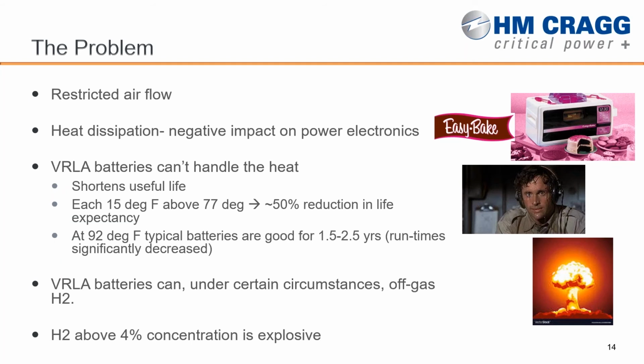VRLA batteries, for example, all of the ratings for life expectancy and what the end of life runtime would be is all calculated based on maintaining a perfect 77 degrees for the entire lifespan of the battery. But for every 15 degrees above 77 degrees you go, you can see about a 50% reduction in life expectancy. So at 77 degrees, batteries, all other considerations perfect, could probably last, let's say, 5 years. But if you go 15 degrees over 77 degrees, up to 92 degrees, you can expect that you're going to start half-lifing. And that 5-year battery is now going to only be about 2.5 years, might be even less, depending on what else is going on within the enclosure, how many times you've had to go to battery, how many discharges, how deep were those discharges. So those are other considerations. So heat in a cabinet, bad.